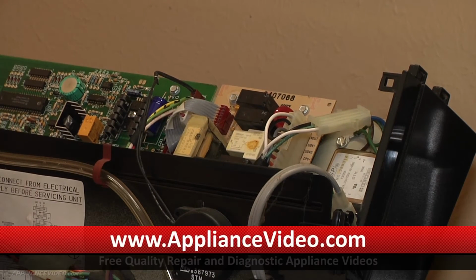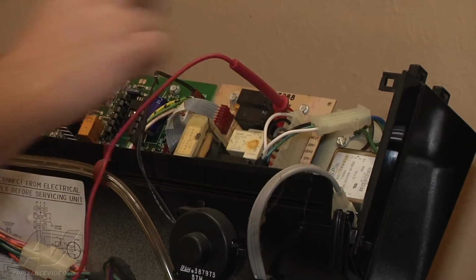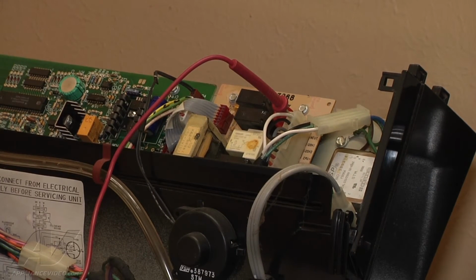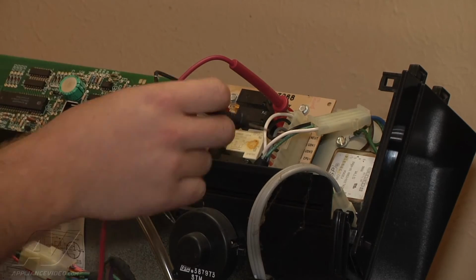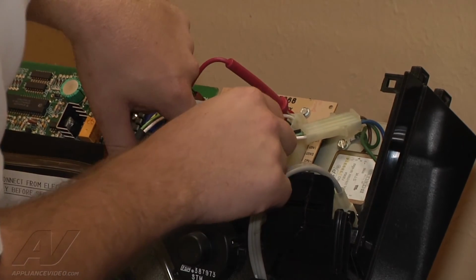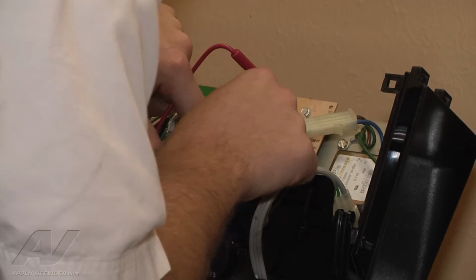So there's kind of a flow chart on where to go if we have correct voltage. After we check that, it wants us to check between pin 1 on the RP3 and pin 5 of the RP1 connection. So we go to pin 1 of the RP3, which was our white wire here, and pin 5 on our RP1 connection, which is down here, the bottom one. We count to the 5th connection, 1, 2, 3, 4, 5, which is our last one, just a gray wire there.